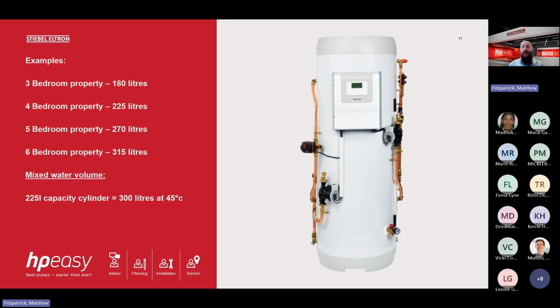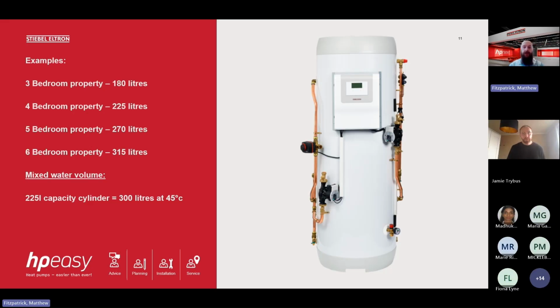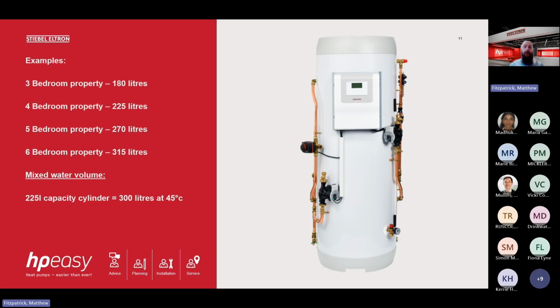When we look at the energy and temperature we actually need in a property for domestic hot water, we are fixated on having 60 degrees at kitchen sinks and coming out of bath taps. It's not required. It's an unusable temperature. It's far too hot. We blend it down to around 45 degrees for kitchen sinks, between 40 and 45 degrees for baths, and around 38 to 40 degrees for showers. So we can achieve a greater mixed water volume. And this has been highlighted at the bottom.